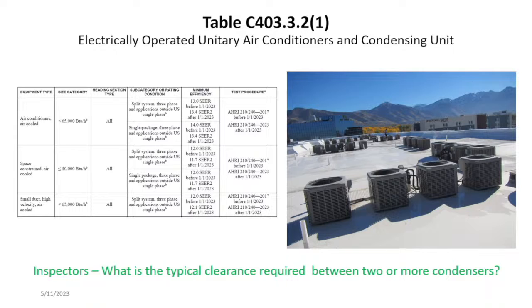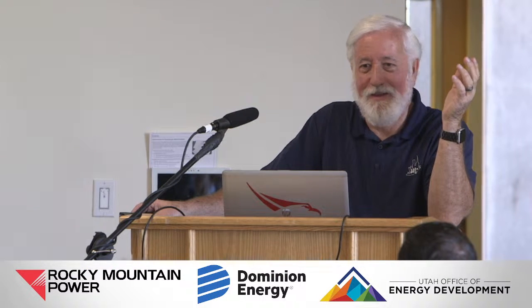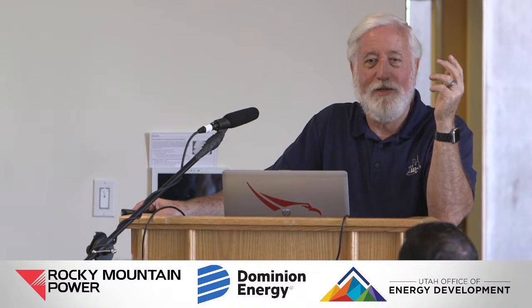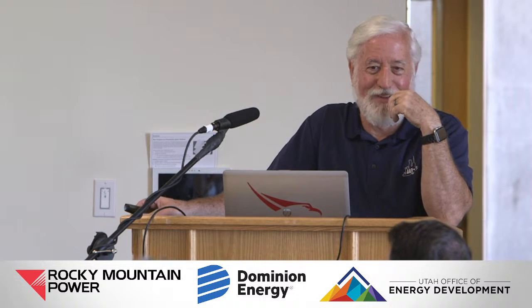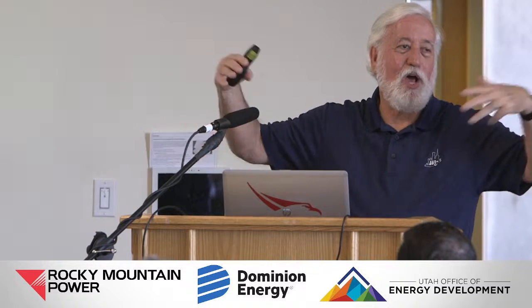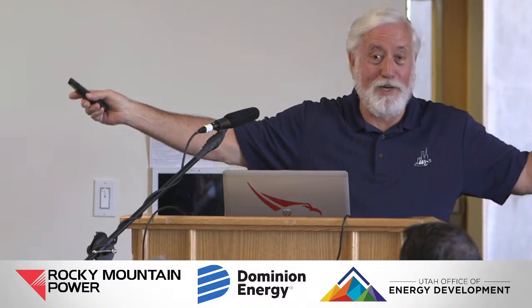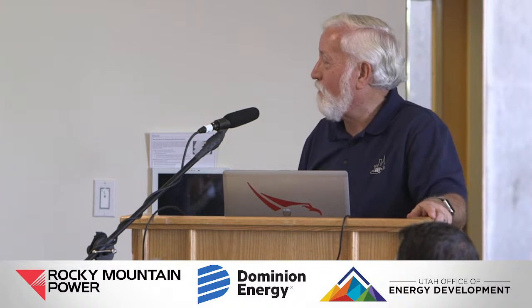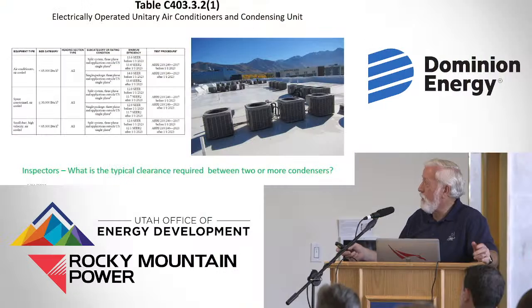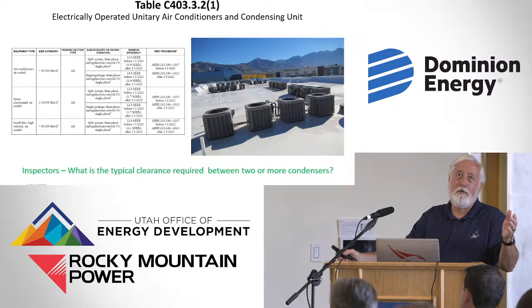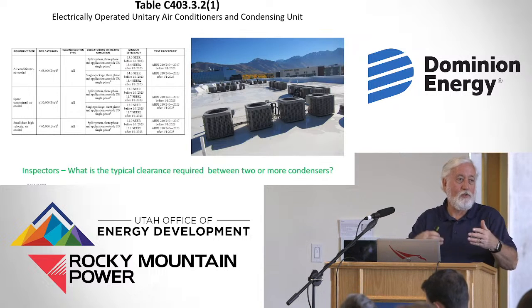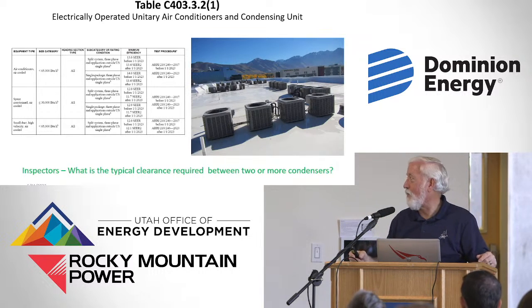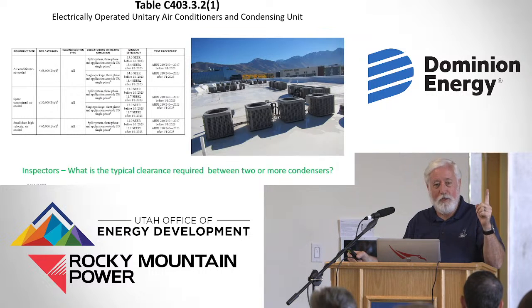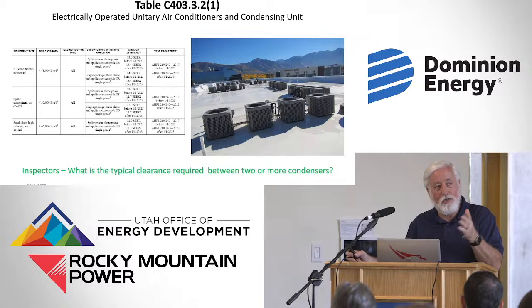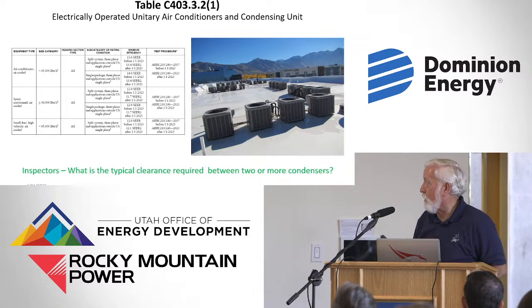Has anybody seen the ads for air conditioner covers? Please, please, please, if anybody sees that ad, please don't buy one for your air conditioner. They're louvers, big louvers that you can hide the unsightly condensing unit, and it's just a bigger box. I don't know what the claim is, but this is actually a big deal. An air conditioner typically requires a minimum 12 inches on all sides. The service side needs to be open so you can get to it, but lots of times you can face it out. A lot of them will allow you to be 6 inches on one of the sides, but you have to have at least 12 on the others. But each unit needs 12 inches of free area so we can get air to it.